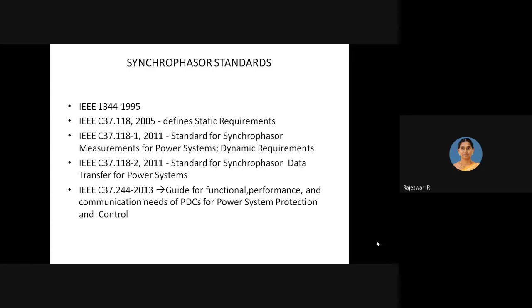A very important concept of total vector error, TVE, was introduced in this IEEE standard, delivered in 2005, which describes the accuracy of synchrophasor measurement. When you are making synchrophasor measurements, there may be chances of error in magnitude or in phase or in both. To combine both types of errors into a single measure, we go for this TVE, total vector error. So this is defined in this particular standard.